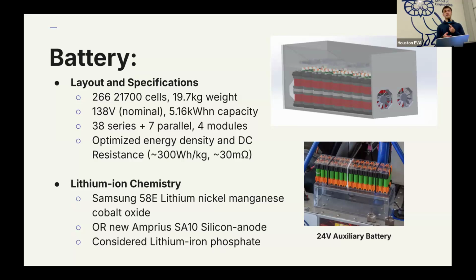Clarifying on the battery design, are you running 4 parallel strings? No, in total it's 7 parallel strings, and the 4 modules are split so that it's 38 divided by 4 in series. Each module has 7 in parallel, and the modules ultimately connect in series to give 38 in series overall.